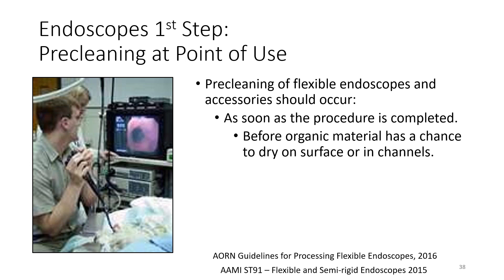So this is a bedside cleaning procedure. You're reducing all those soils and preventing drying, but you got to have the PPE. You have to be doing it immediately after the insertion tube is removed from the patient. You have to have your solution, whether it's water or enzymatic. You have to do your external wiping and you have to take care of the channels. And most importantly, you have to follow the manufacturer's instructions for use on this pre-cleaning procedure.